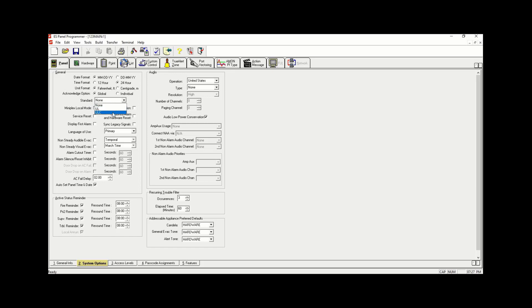For standards, UL is designed for the American standard and ULC is designed for the Canadian standard, so we're going to choose ULC. We're going to choose System Reset Service Reset, combined alarm and hardware reset, and Display First Alarm. Then we're going to check Alarm Silence Inhibit and leave 60 seconds as default. The AC Fail we're going to change from two hours to five minutes, and we're going to uncheck all the reminders with the exception of Trouble Reminder.